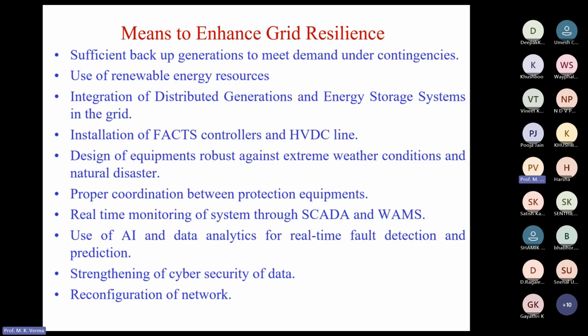There must be proper coordination between protection equipment. We have seen the example of the July 30th and 31st, 2012 blackout, where almost the whole part of the country was disturbed for hours. If there had been proper coordination between the relays, you could have avoided that amount of interruption. You should have real-time monitoring of the system through SCADA and WAMS.